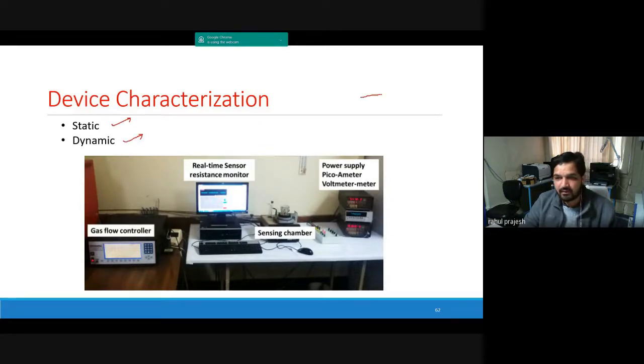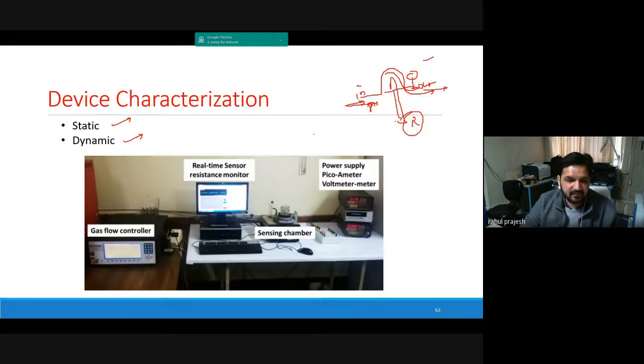So what is static? You have a chamber. It has an inlet and an outlet. You close the outlet and just input the gas inside, and you have a sensor inside, and you measure the resistance. This is the static measurement. Once the measurement is done, you open the outlet and flush the gas out of the chamber. But in dynamic measurement, what happens? You have a continuous input and continuous output of the gas. So there are two measurements, and in different cases, different measurements are required.